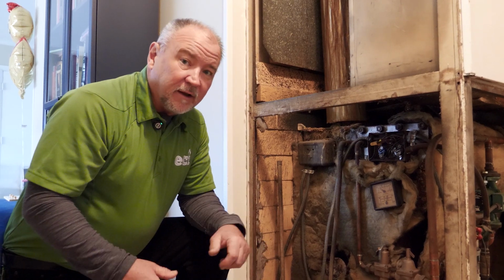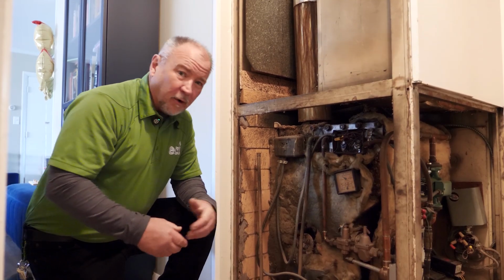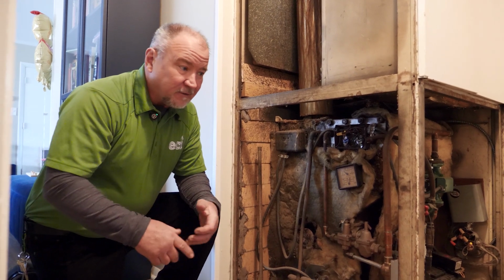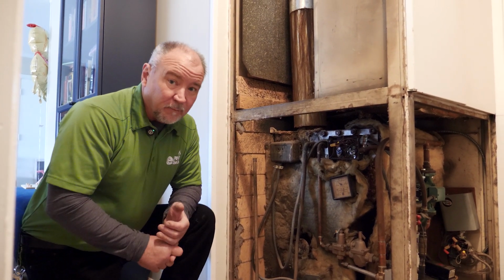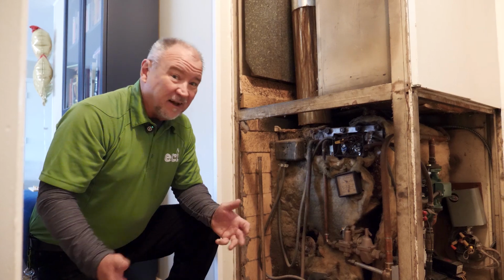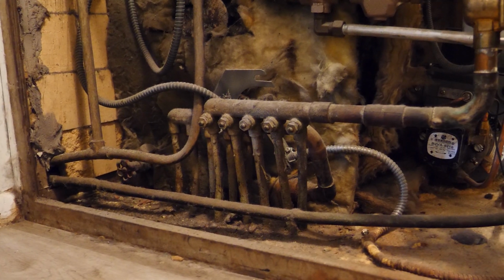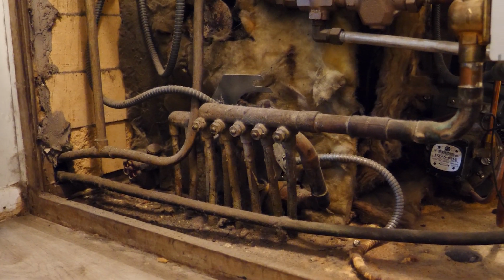Today, we still do radiant heat. Radiant heat is the most efficient and most comfortable heat that you can put in your home today, regardless if it's heated through oil, gas, electric, a heat pump. Heat and hot water, put it in the floor, there's nothing more comfortable. I mean, I can feel this floor, it is warm. As soon as you put your feet on it, bare feet, you're instantly warm. Basically, we don't want to put high temperature water into the floor. 130, 140 is usually the ideal. Even 120 is a better temperature for your floor heat.